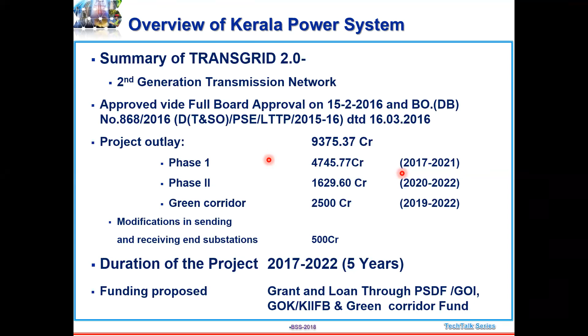So the TransGrid project is mainly meant for satisfying the contingency criteria, so that there will not be any failure of the system in the event of failure of one of the network elements. We are planning a 400 kV pan-Kerala grid from north to south for transporting the power requirement of central and north Kerala. As I told you earlier, all our sources are in the southern part, so this power has to be transported to the northern part with minimal loss. Along with that, we are upgrading the existing downstream networks also, 33 kV, 66 kV, and 110 kV networks. It is planned in two phases.